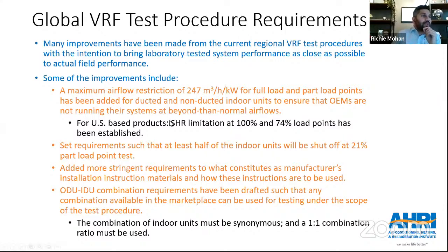The first thing we've added is the airflow restriction, on the indoor side. The indoor airflow for both ducted and non-ducted VRF equipment is going to be capped at 247 cubic meters per hour per kilowatt. You're not able to go beyond these airflow levels during testing. This was, of course, after reviewing what would be the normal airflows you'd see in the field for typical VRF operation.